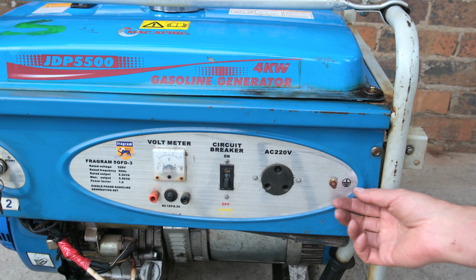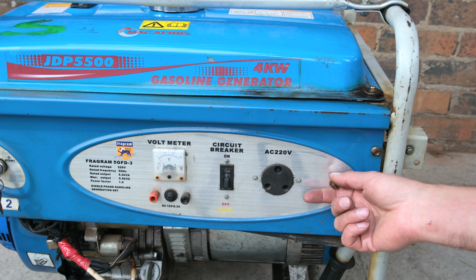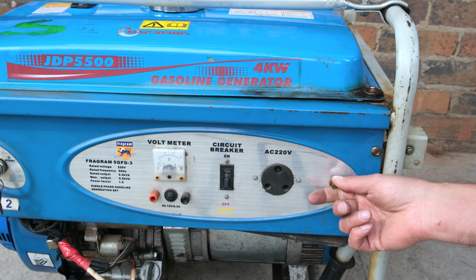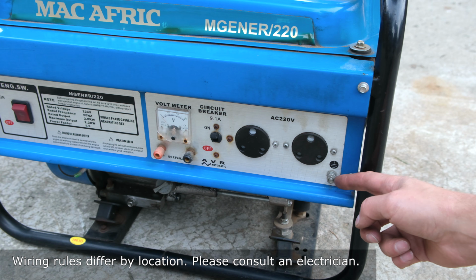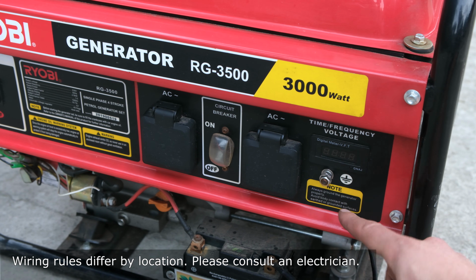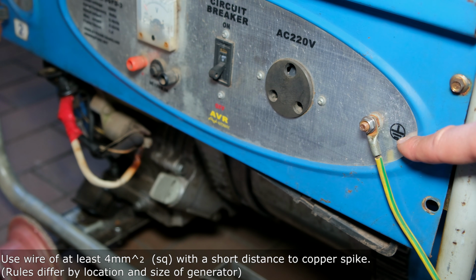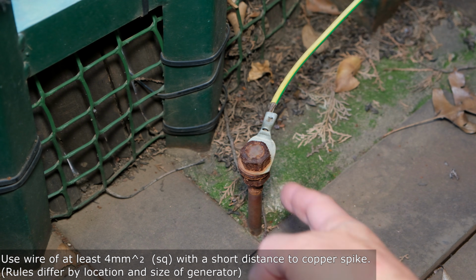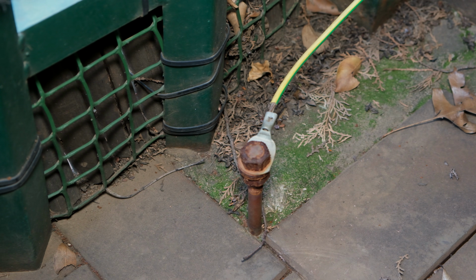On the chassis of every generator is an earth point. Make sure the earth point is electrically connected to an earth spike in the nearby vicinity of the generator. There's the earth point on this generator, and here it is on this one. Here's an example of a generator being earthed. The earth wire is connected to a nearby copper rod. That copper rod is hammered into the ground for earthing.